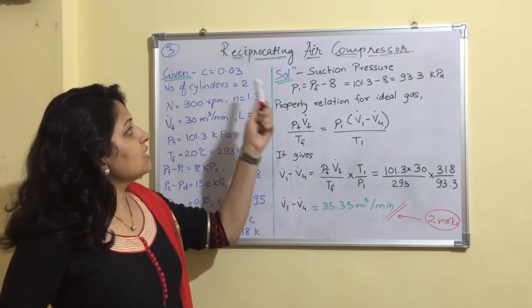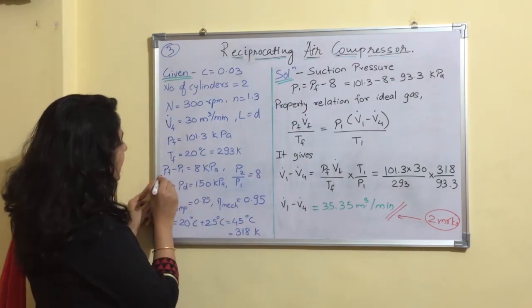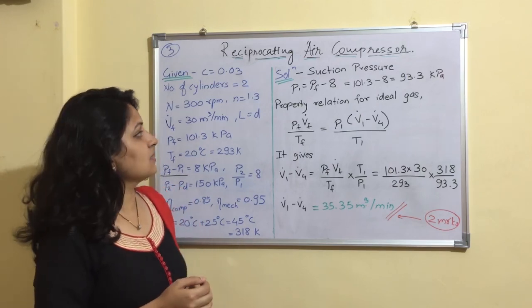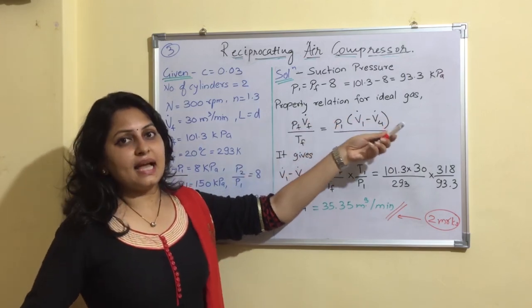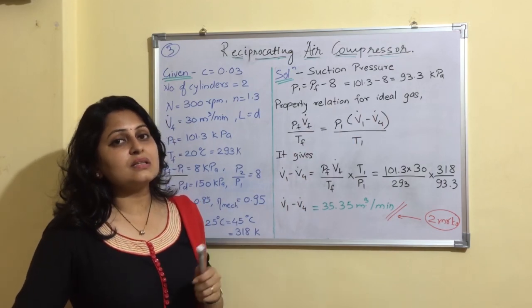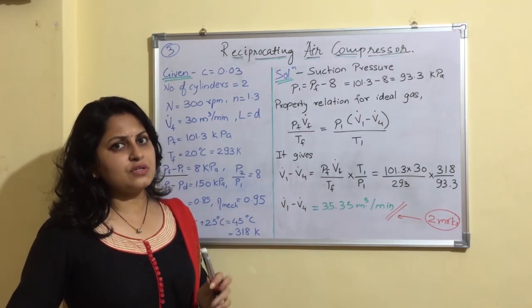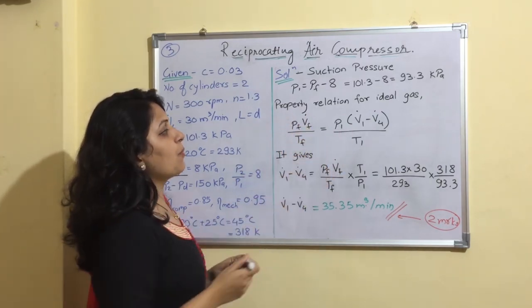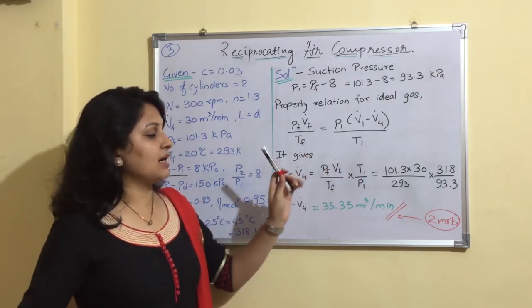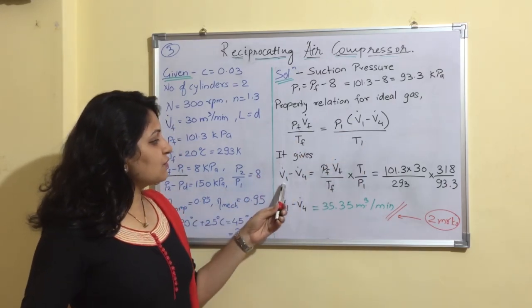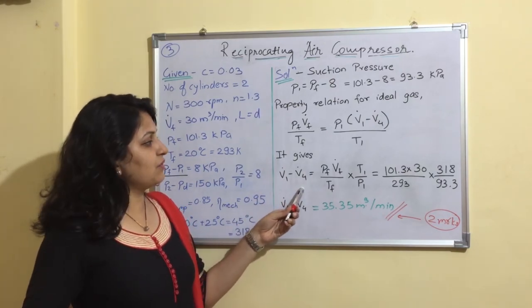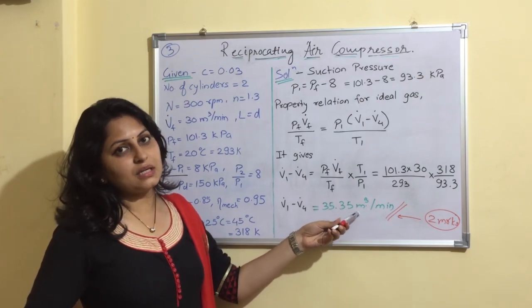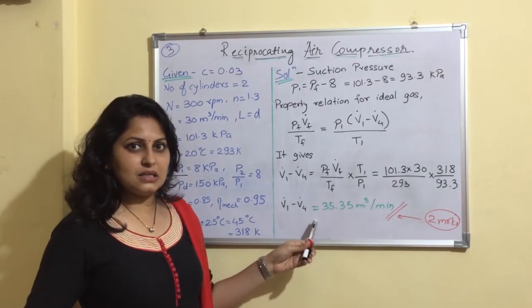First, we find suction pressure using the inlet pressure loss: P1 = 101.3 − 8 = 93.3 kPa. Then, from the ideal gas relation PV = mRT with m and R constant, we use (P_F · V_F)/T_F = (P1 · V1)/T1 to find (V1 − V4). Substituting all values, we get (V1 − V4) = 35.35 m³/min.